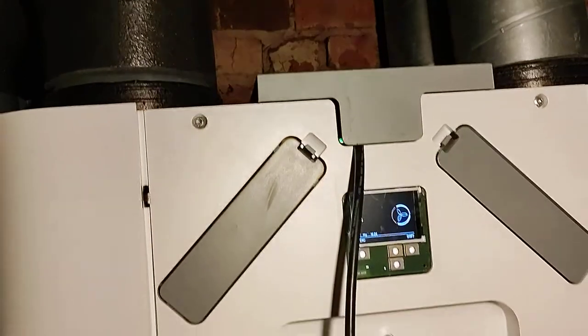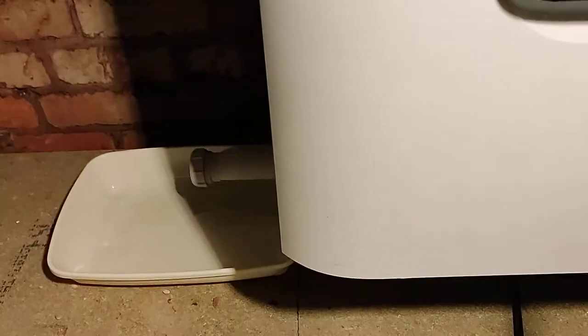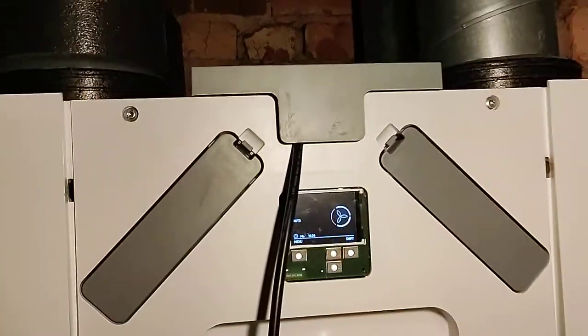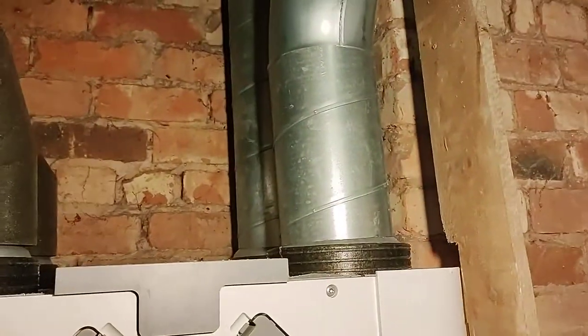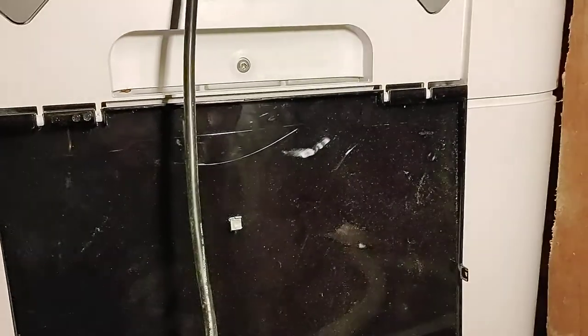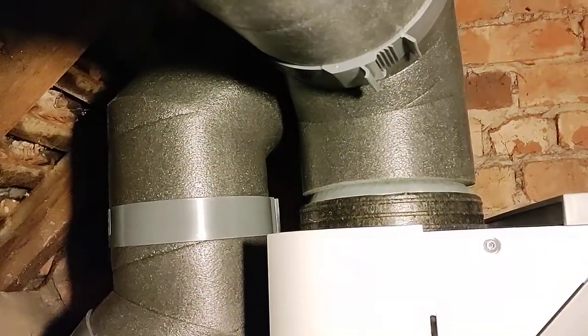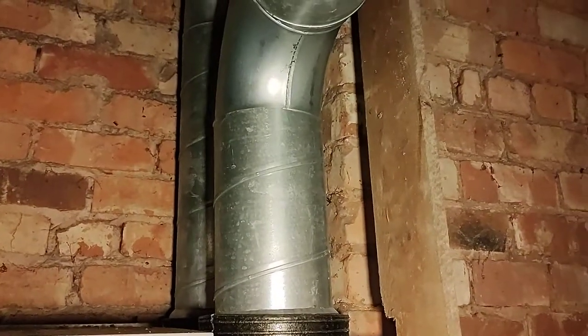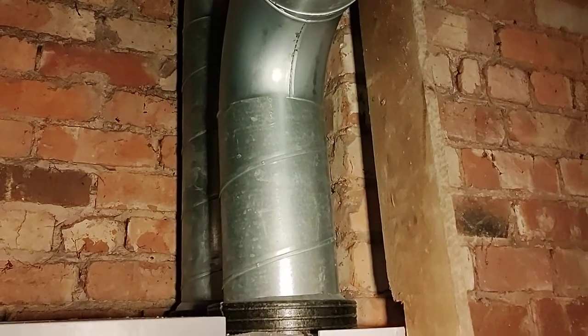So what's actually happening here, and what's generating this water, is that warm, humid air is leaving the house through the ductwork. It's entering into the heat exchanger, where it's passing its heat to the incoming air, the fresh filtered supply air. That fresh air is going back into the house, where it's tempered and nice and warm and comfortable. And then the now cool air is going to outside.